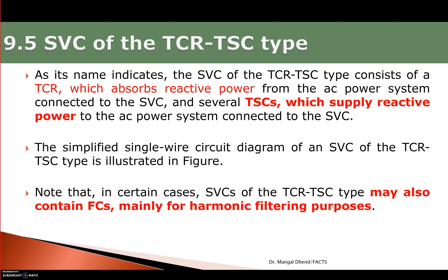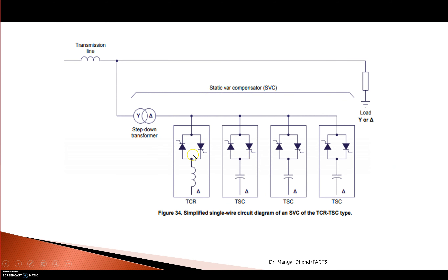In an SVC of the TCR-TSC type, when TCR is functioning it absorbs reactive power, and when TSC is in major functioning it supplies reactive power. The total power of the SVC will be whatever is generated by TCR minus TSC, because TCR absorbs power (positive) and TSC supplies power (negative). So total power QT equals QL minus QC. In the simplest wiring diagram one branch is shown, but it does not mean only one is used.